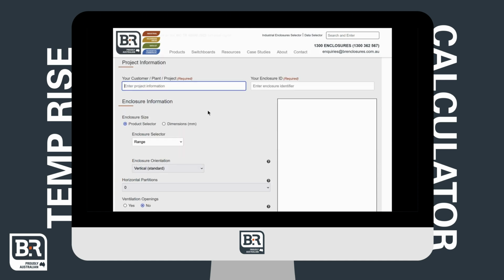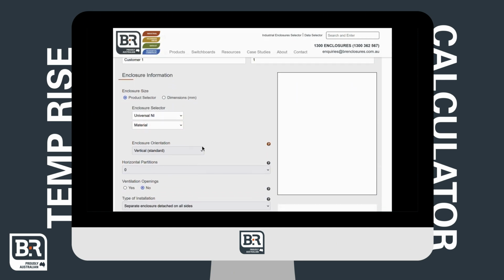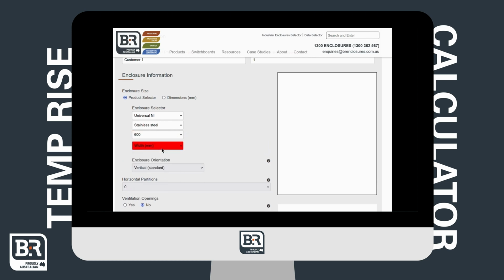Users begin by entering customer and project details. This is purely for record keeping. In this example, customer 1 and enclosure ID 1 are entered. The scenario requires a stainless steel enclosure 600 mm wide mounted between two others exposed to sunlight, and housing 4 electronic devices at 30 watts each. These devices have a 75-degree temperature limit.